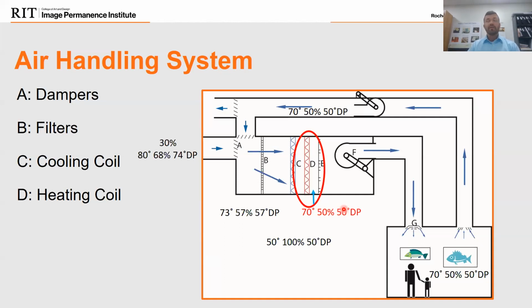No, it depends. There are a number of factors. It depends on the design of your mechanical system. I laid out a standard mechanical system in this process just to give an idea of what each component does. This is what they call a subcool reheat. There are some air handling units where these coils are flipped and it's either heating or cooling only. Really, it depends on the type of air handling unit that you have and the way the system is laid out. I will give some examples of different units in a few minutes, and it may help give some impression of what other types of units will look like. But this is just a standard subcool reheat, not what every unit looks like.